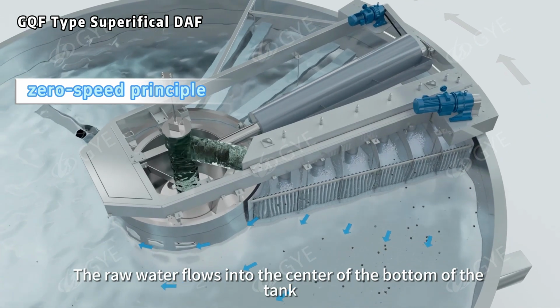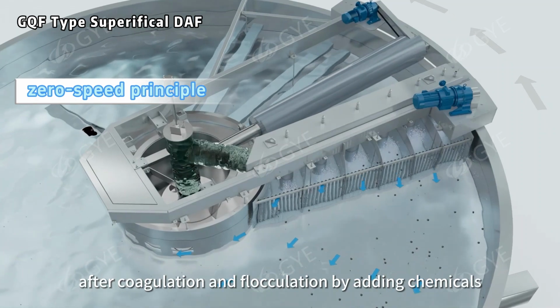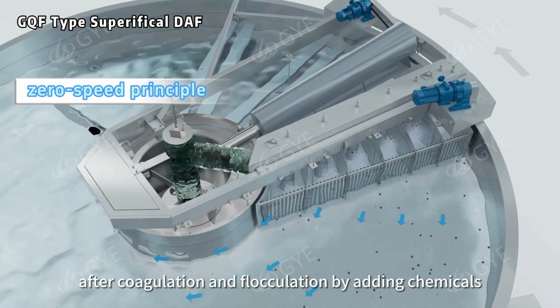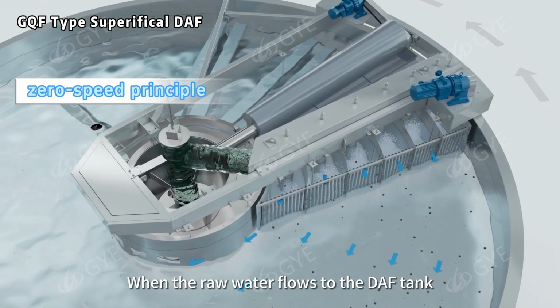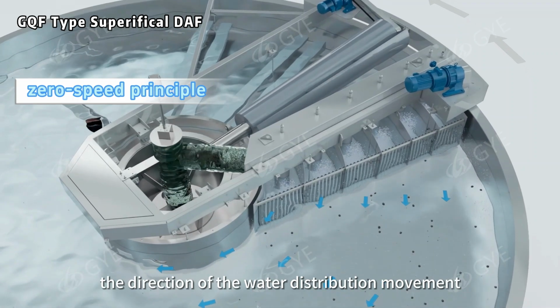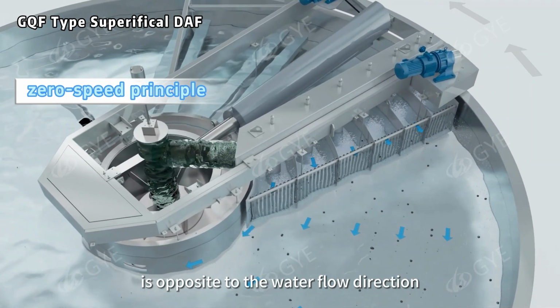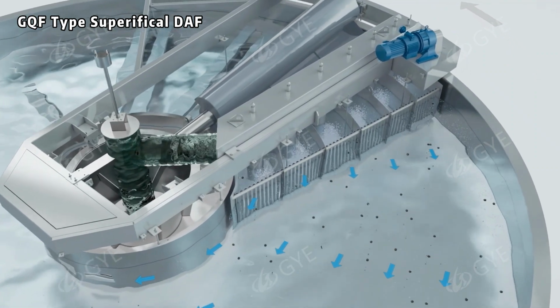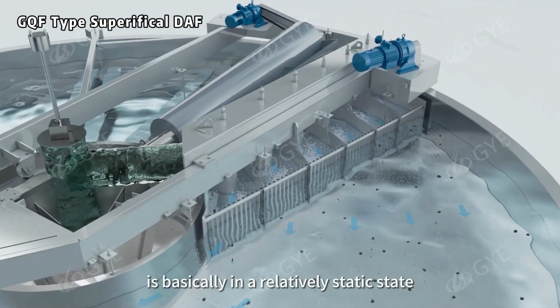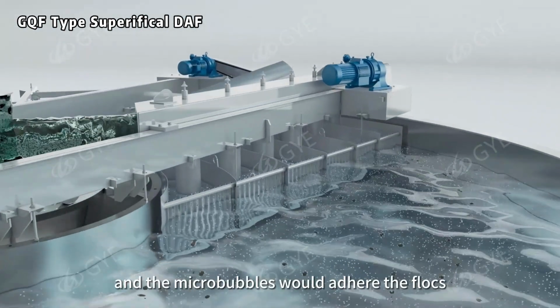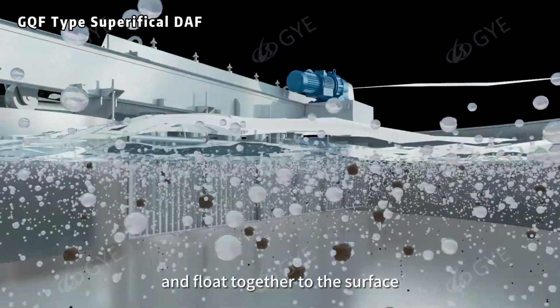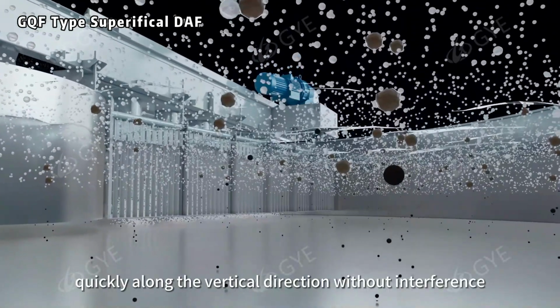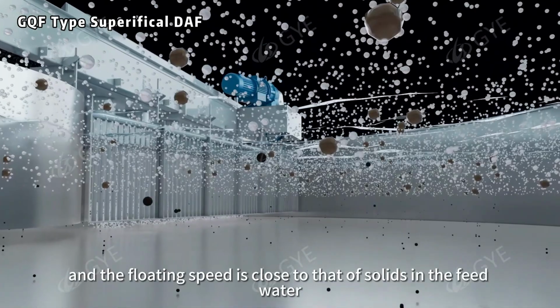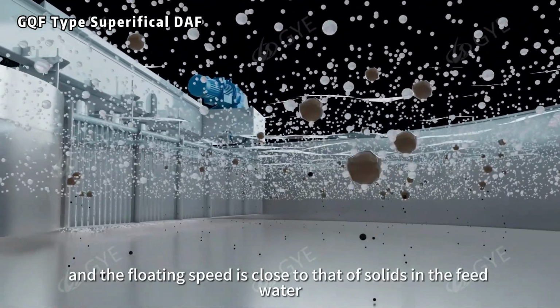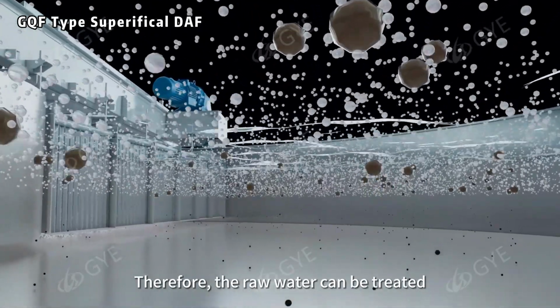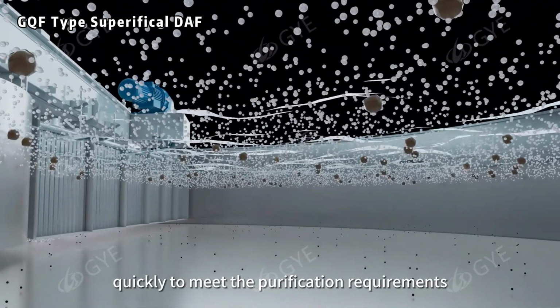The raw water flows into the center of the bottom of the tank after coagulation and flocculation by adding chemicals. When the raw water flows to the DAF tank, the direction of the water distribution movement is opposite to the water flow direction, and their speed is similar. The raw water in the DAF tank is basically in a relatively static state, and the microbubbles would adhere to the flocs and float together to the surface quickly along the vertical direction without interference, and the floating speed is close to that of solids in the feed water. Therefore, the raw water can be treated quickly to meet the purification requirements.